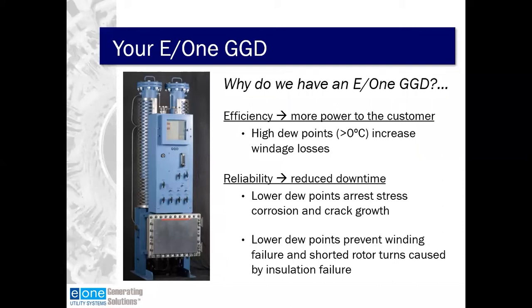So the first issue we have is efficiency. As with higher dew points in your generator and your hydrogen gas, in this case, those higher dew points would be above 0 degrees centigrade, they increase the windage losses. And what that means is, we talked about hydrogen having the lowest density of any gas. Once the dew point gets to 0 degrees C and higher, that quantity of water vapor in the hydrogen starts to affect the density of the hydrogen. And that density impact results in a lower efficiency for the generator.